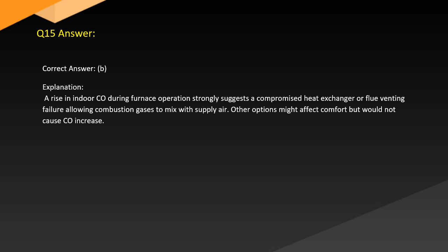Answer. Correct answer: B. Explanation. A rise in indoor CO during furnace operation strongly suggests a compromised heat exchanger or flue venting failure, allowing combustion gases to mix with supply air. Other options might affect comfort but would not cause a CO increase.